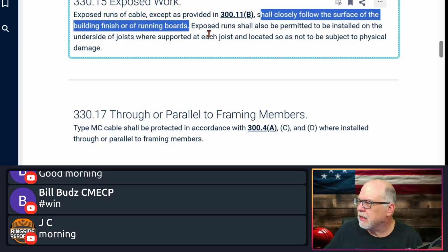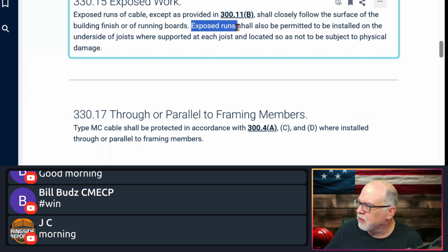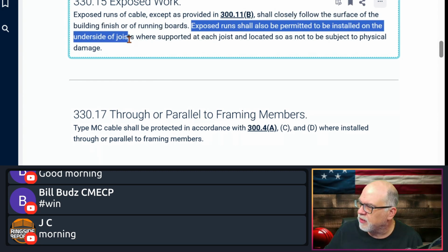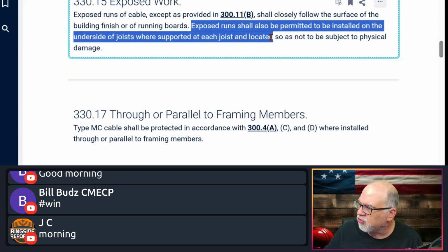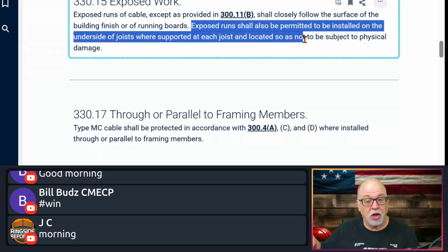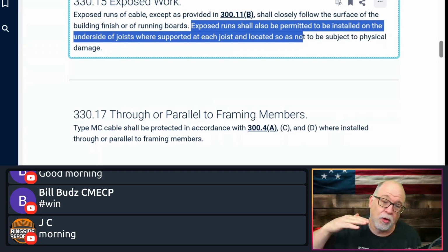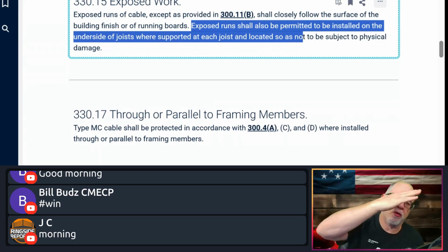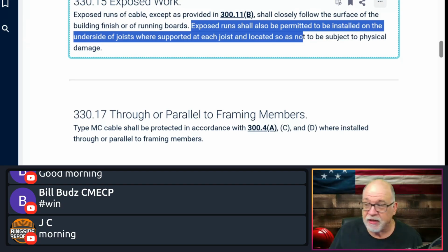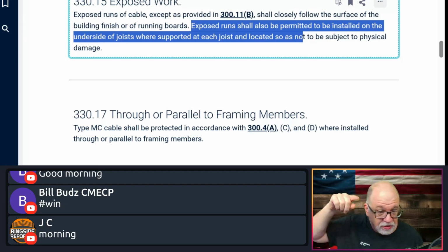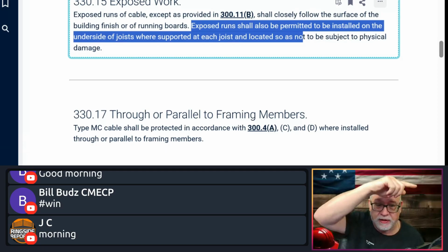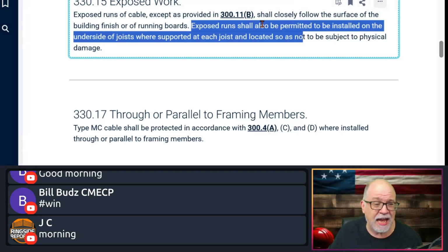All right, so it says exposed runs shall also be permitted to be installed on the underside of joists where supported at each joist and located so as not to be subject to physical damage. So can I run them under the floor from joist to joist to joist? Absolutely I can, as long as I'm doing what? I'm supporting it at each joist. So it's a lot of straps, by the way, every joist, okay? And it has to be where it's not subject to physical damage.